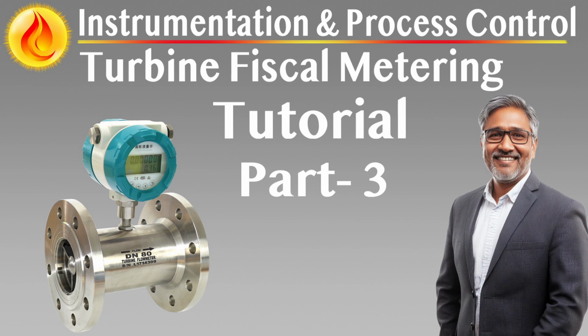The strainer must feature a flanged quick-release closure, ideally with a davit arm or hinged mechanism, to facilitate easy removal of the basket without requiring extensive disassembly or special tools. Vent and drain ports must be included to safely depressurize and drain the housing prior to opening. These connections must be flanged with proper sealing and pressure rating consistent with the process line.